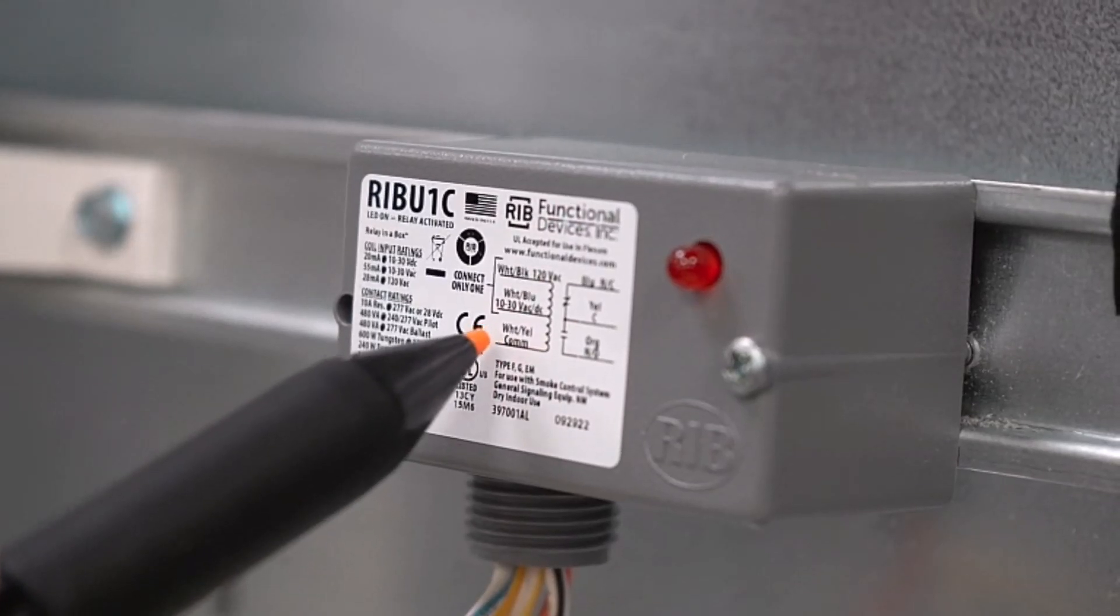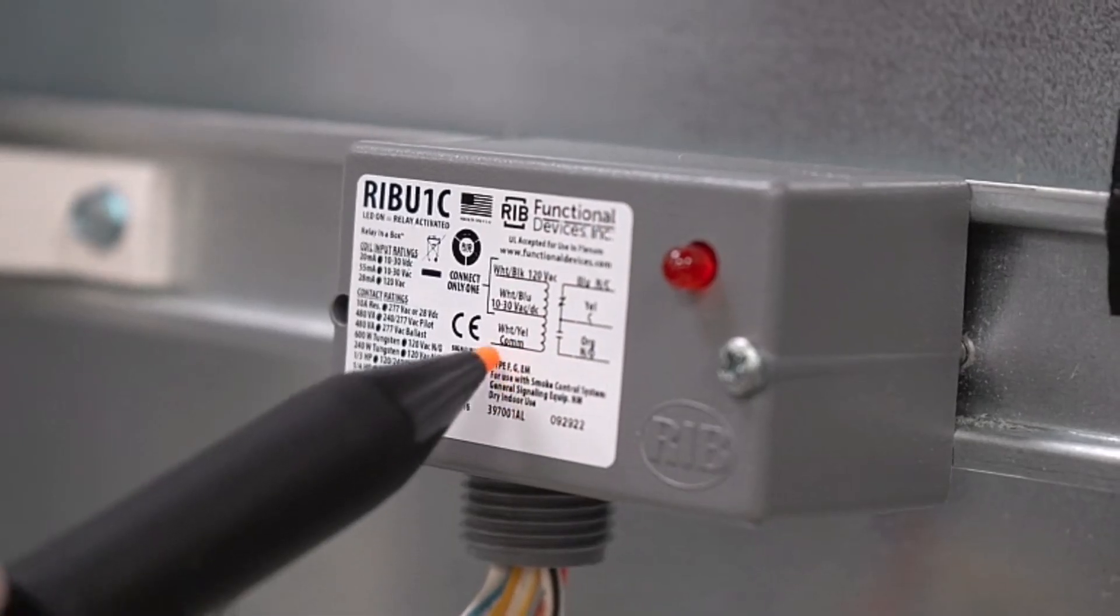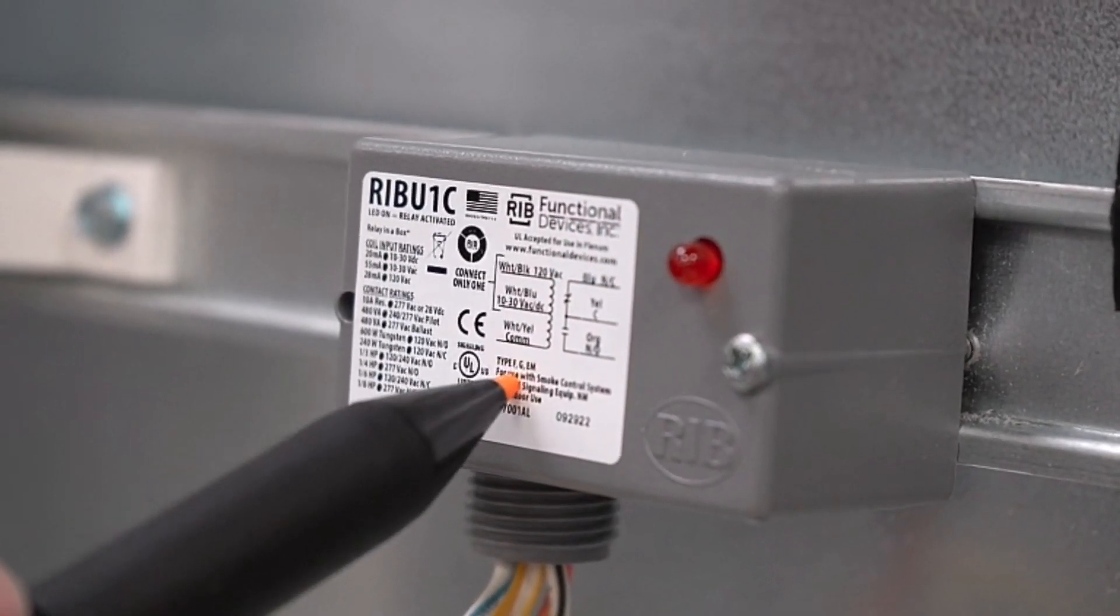So for our scenario here with the UC600, we're going to use 10 to 30 volts DC, so white and blue wire. Then we also have to complete our path for our white and yellow for our common.